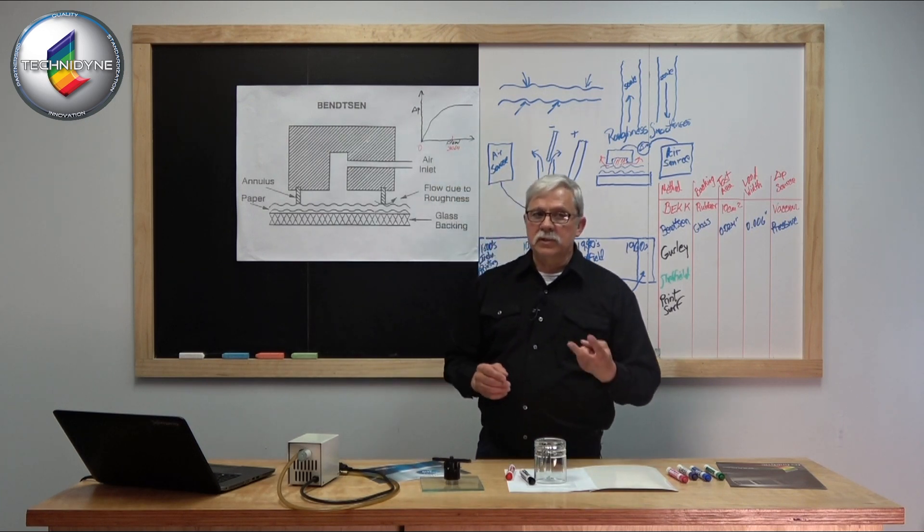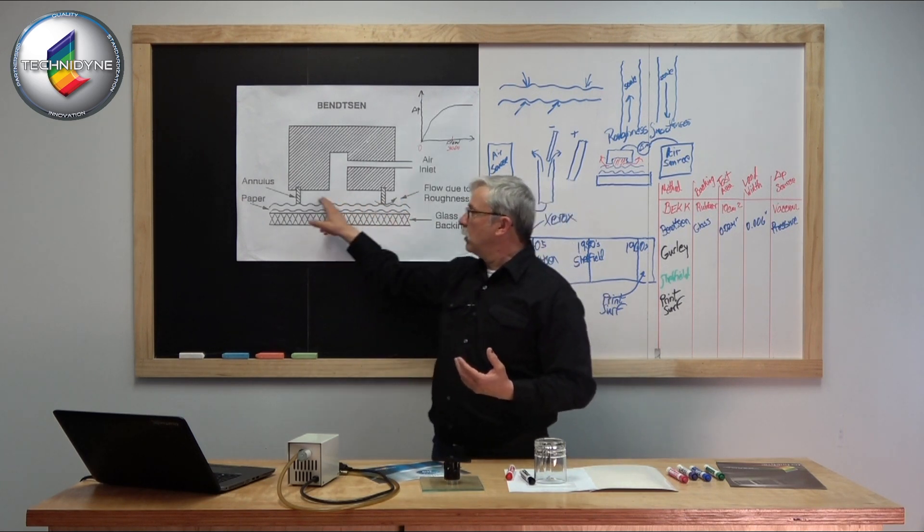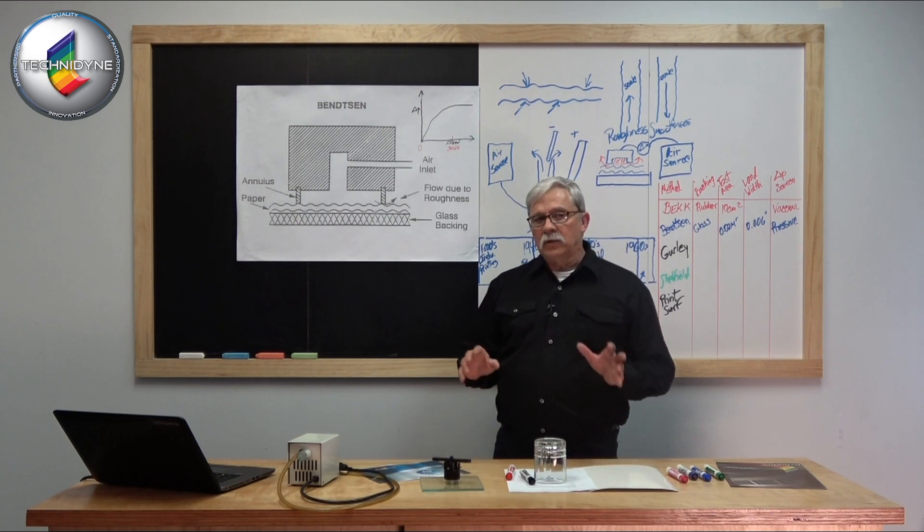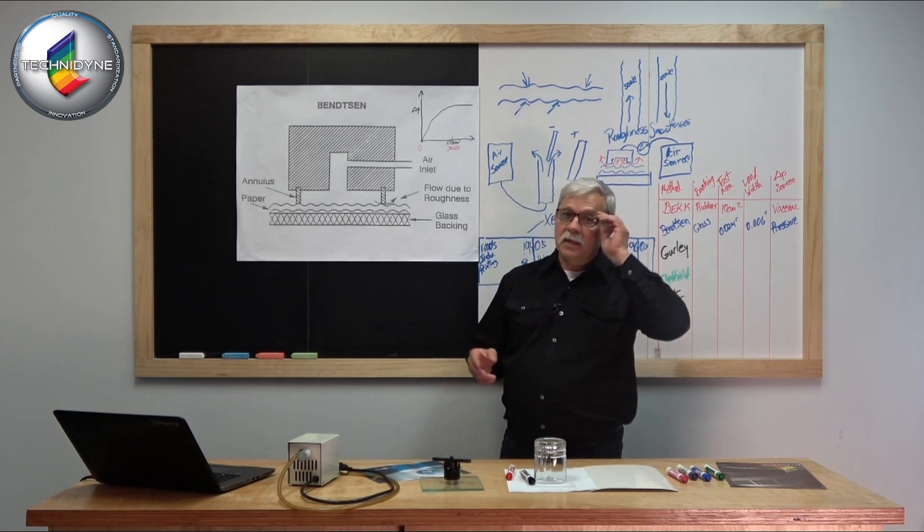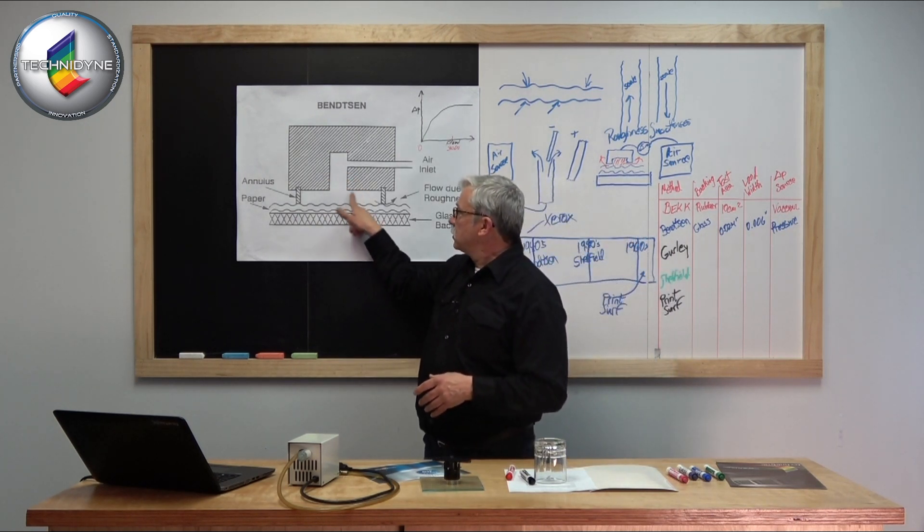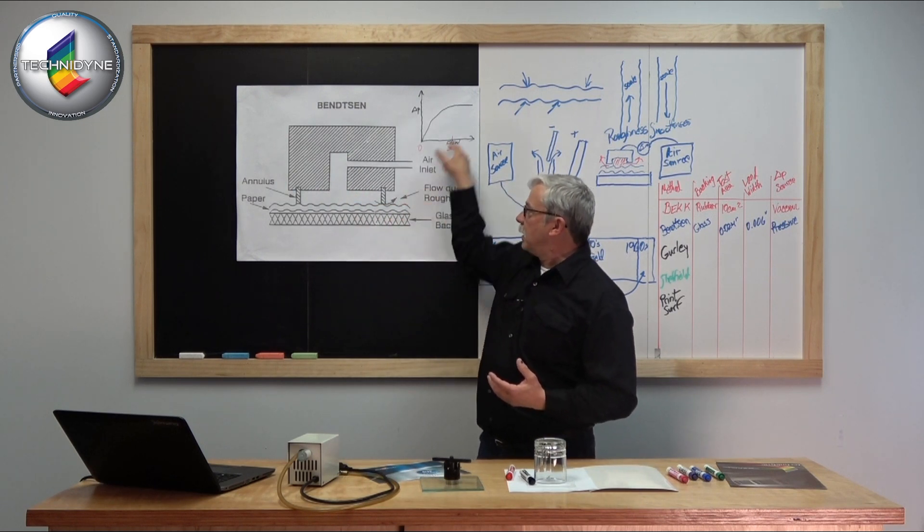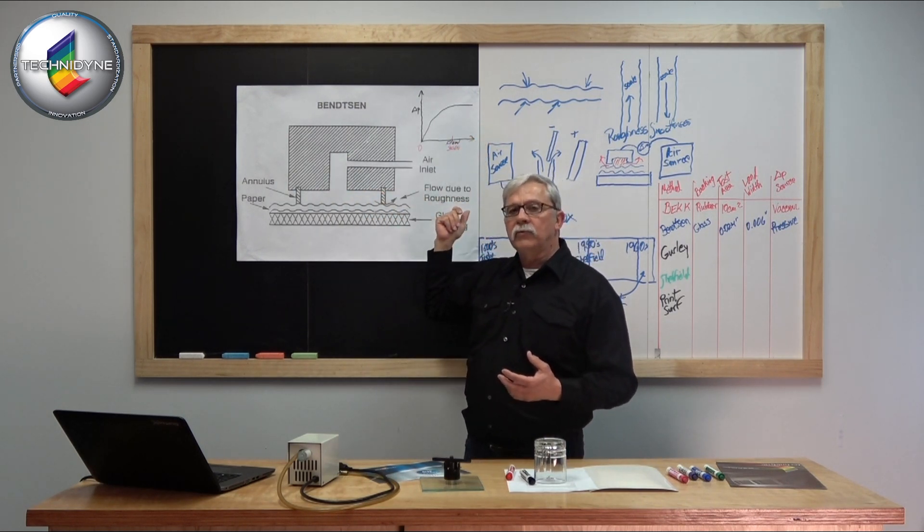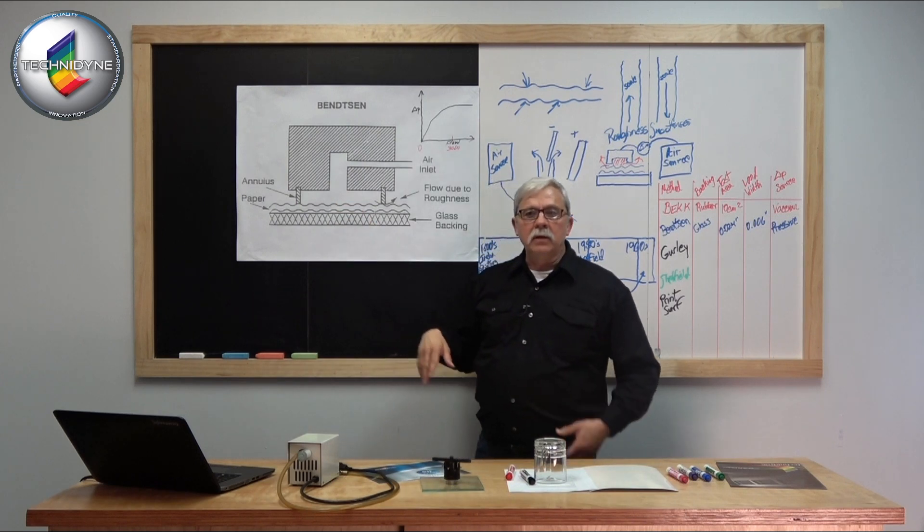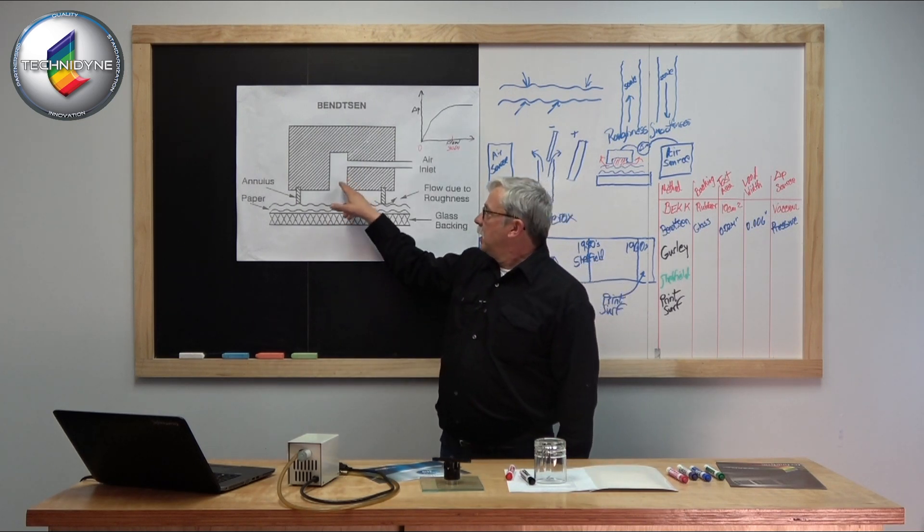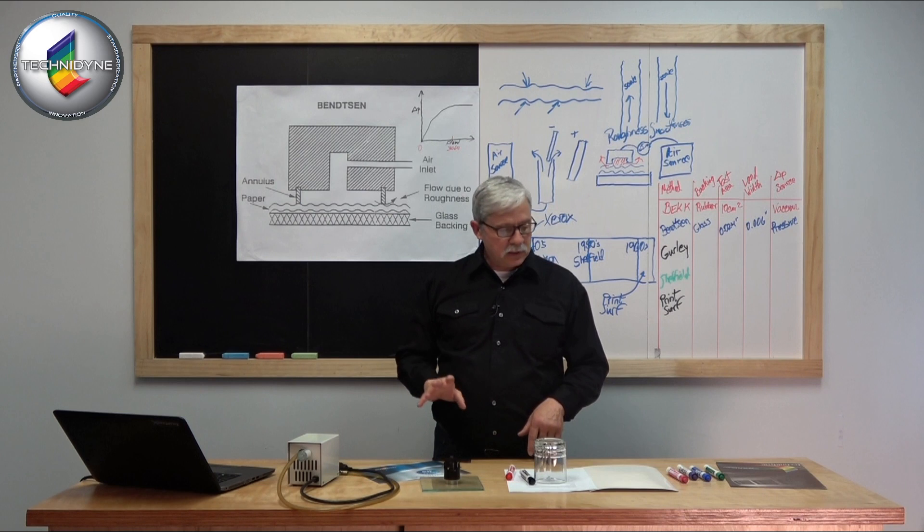You could imagine that if I have two systems, one regulating at 1 PSI, I'm going to get a certain flow out from underneath my annulus. If I have another system that for whatever reason couldn't maintain 1 PSI, maybe I've got 1.25 PSI, that's going to charge this area under here higher. My pressure differential between my captured area and atmosphere is going to be higher, introducing higher flow. Simple as that. If I can only maintain 0.75 PSI, I'm going to get less flow out from underneath here. We have to maintain all those critical parameters to reproduce this test over and over again.